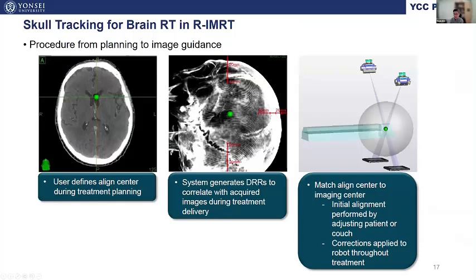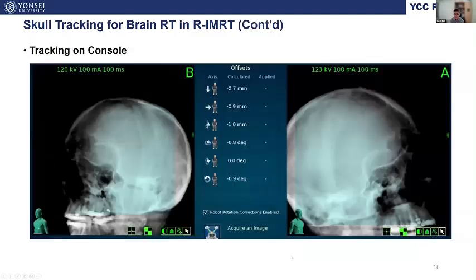For brain radiosurgery, skull tracking is used in most cases, working as follows. The user can define the align center during treatment planning, which is recognized in the process of DRR image generation. Tracking is performed by comparing and matching the skull placement in DRR and kV X-ray images. You can see the following images displayed in the treatment console as an example, which produce the offset values, indicating how much the couch needs to be translated and rotated.